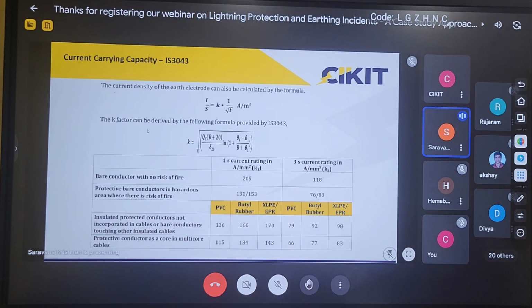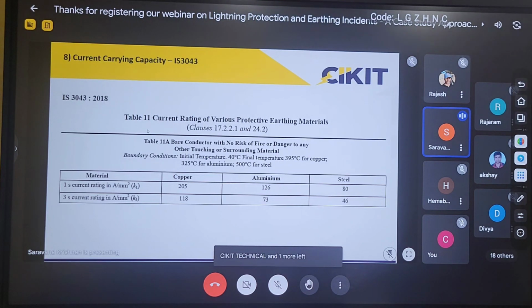So from this, we can observe that the two other parameters are the cross-sectional area and the factor K. So the K depends upon the material and the duration. I have provided the table from IS 3043. So here I have shown the comparison from IS 3043. Here you can observe that they have provided values for copper, aluminum, and steel, and they have provided the value of K for 1 second as well as for 3 seconds. So for copper, the value of K will be 205 for 1 second, and for steel, the value will be 80 for 1 second. Whereas for 3 seconds, for copper it will be 118, and for steel it will be only 46. So the value of K itself will be different for different time periods.